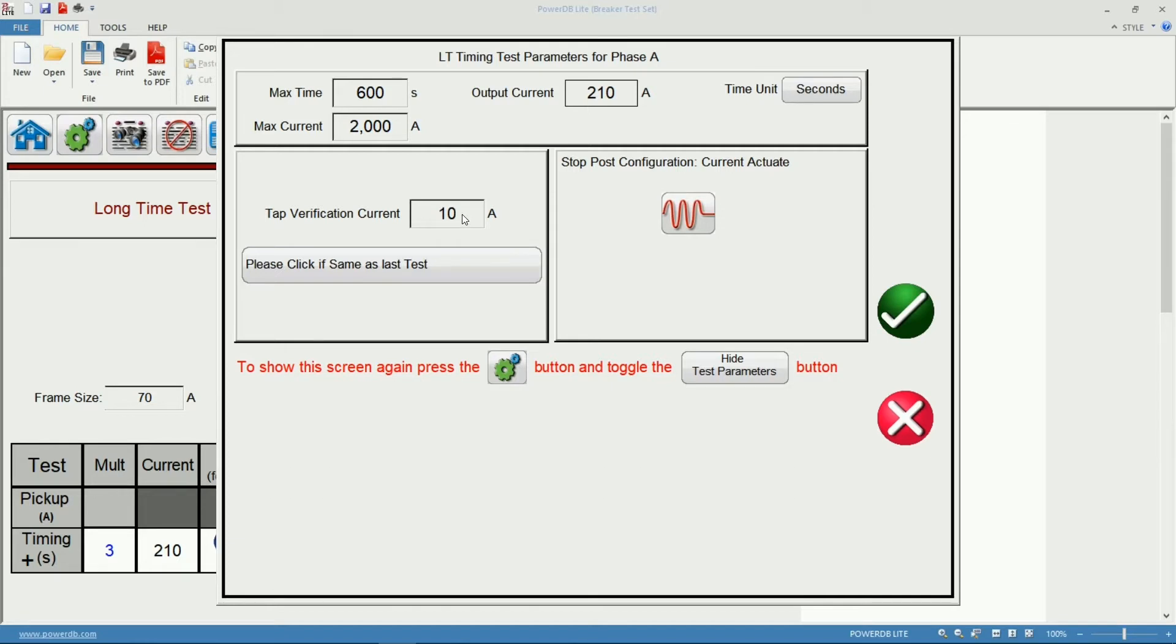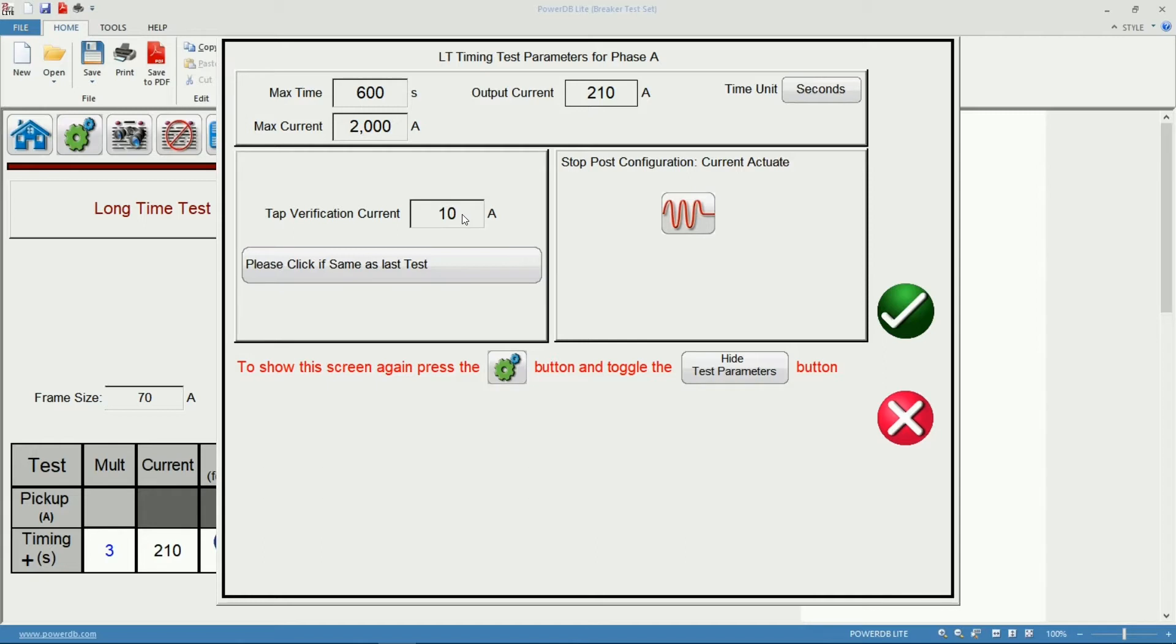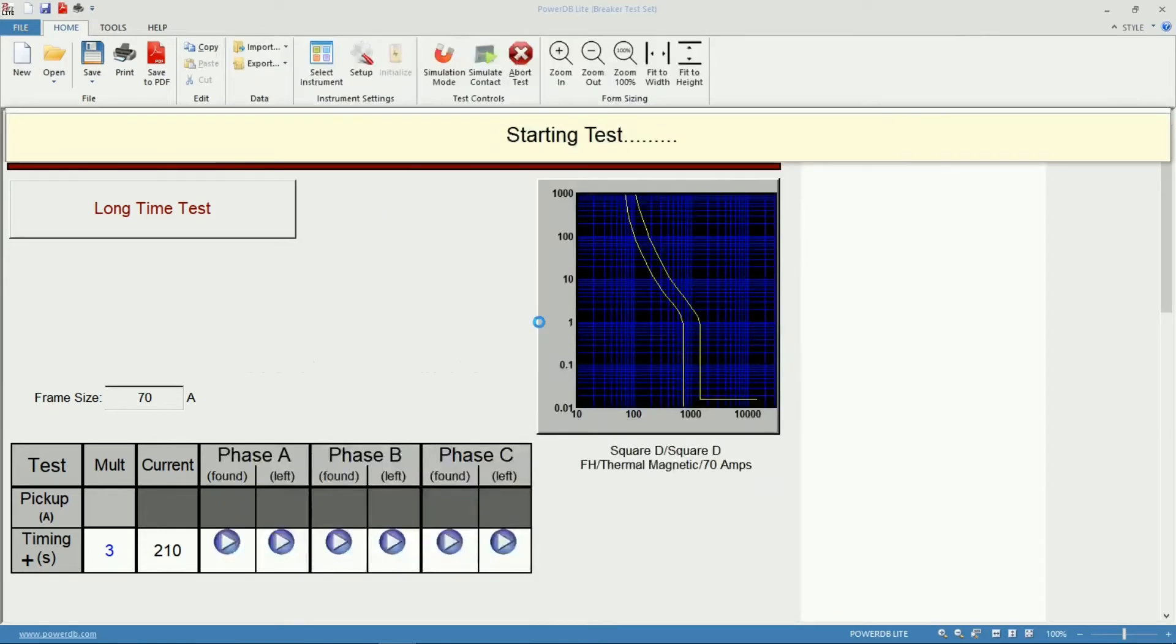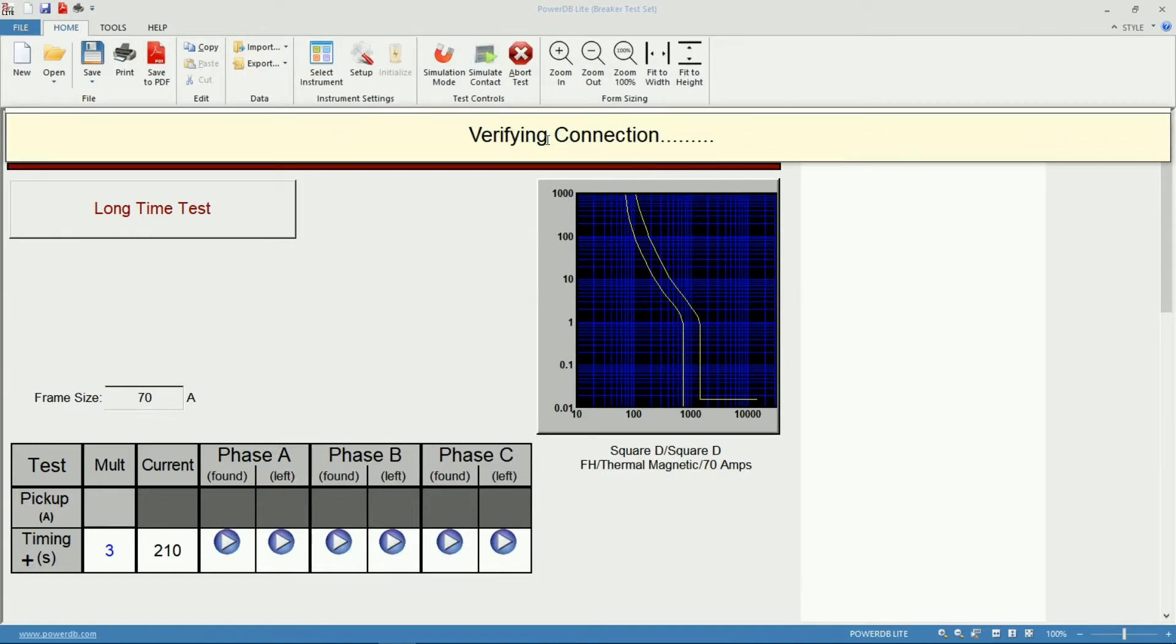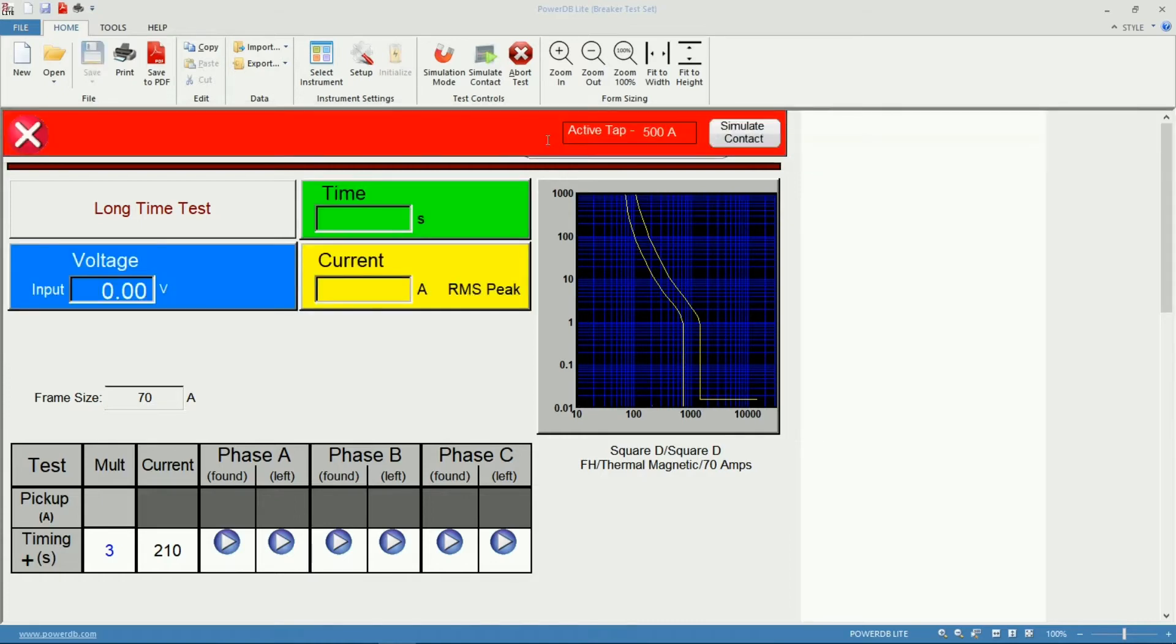This is the current that the unit will use in that pre-injection to determine the impedance of the circuit connected to the output of the SPI so that the unit can adjust the output accordingly and inject the 210A in this case. I'm going to accept the settings. The unit will start the test, verifying the connection, finding the TAP in use, calculating the impedance, then inject the current.